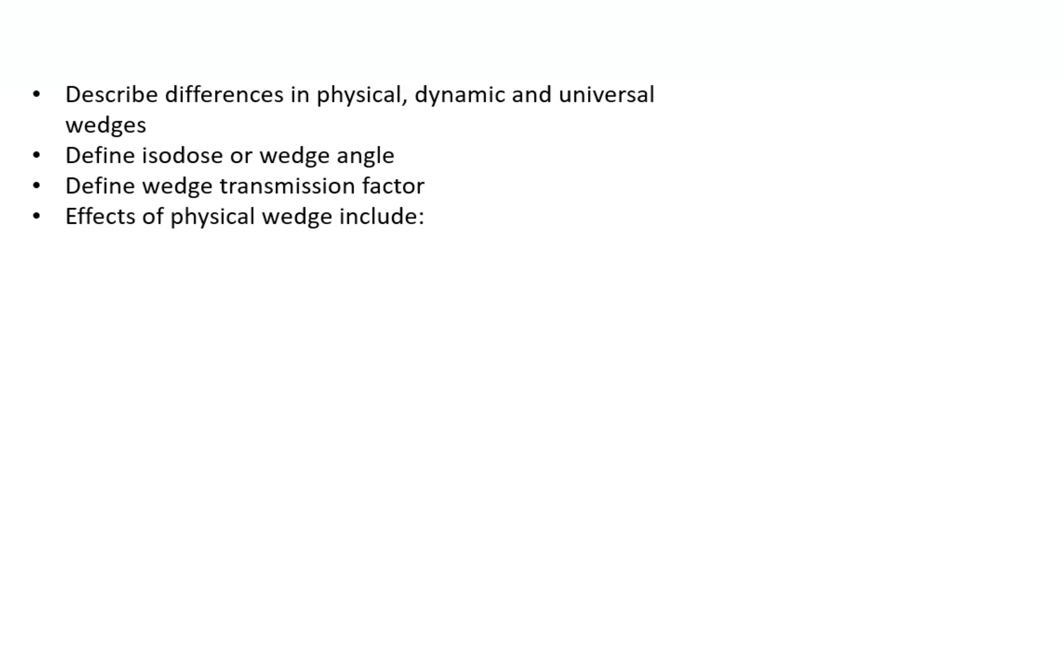So what is a wedge angle? The wedge angle is the angle through which an isocurve is tilted at the central ray of a beam at a specified depth, typically 10 cm.